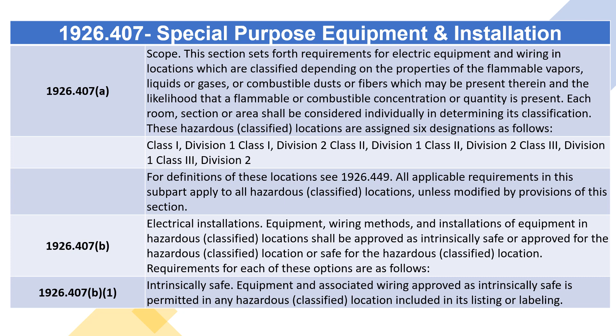1926.407(b) Electrical Installations. Equipment, wiring methods, and installations of equipment in hazardous, classified, locations shall be approved as intrinsically safe or approved for the hazardous, classified, location or safe for the hazardous, classified, location. Requirements for each of these options are as follows. 1926.407(b)(1) Intrinsically safe. Equipment and associated wiring approved as intrinsically safe is permitted in any hazardous, classified, location included in its listing or labeling.